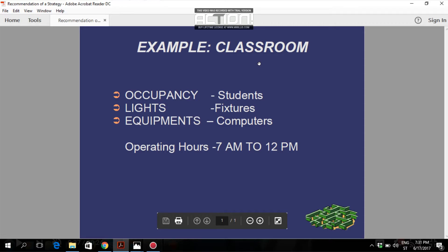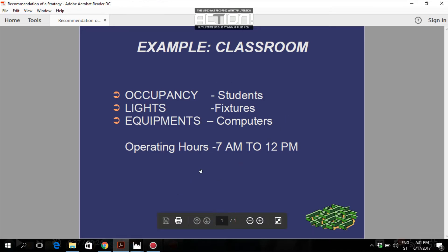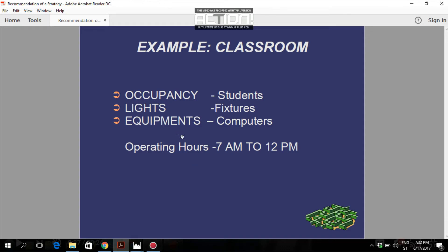As an example, consider a classroom with three components: occupancy — meaning human presence, the students; light — the fixtures; and equipment — the computers. The number of students equals the number of chairs inside the classroom. The light fixtures are located on the false ceiling. Let's assume the operating hours of this classroom are 7 to 12 PM, which is five hours daily. This means these three components contribute heat load only during those five hours.